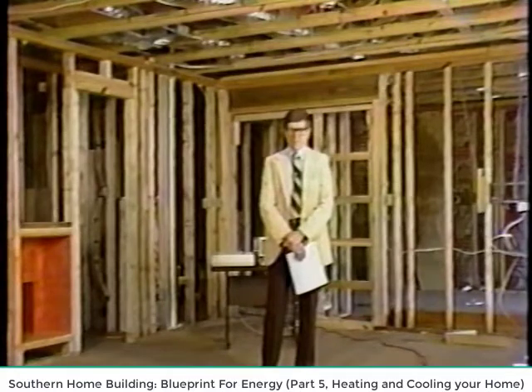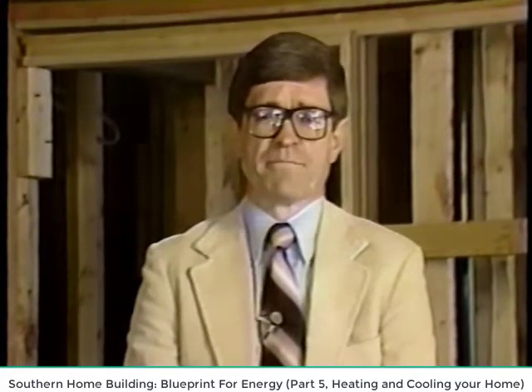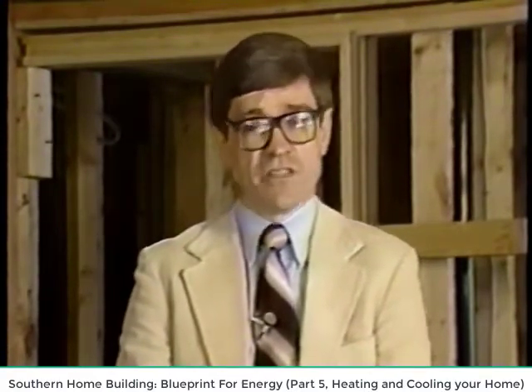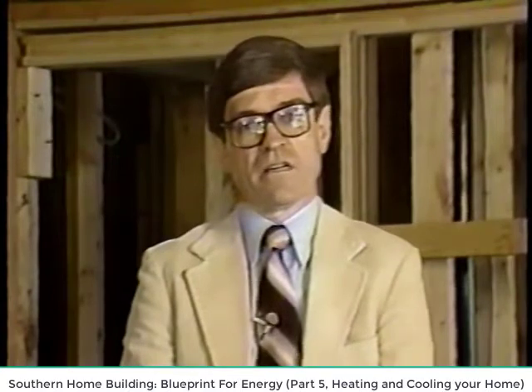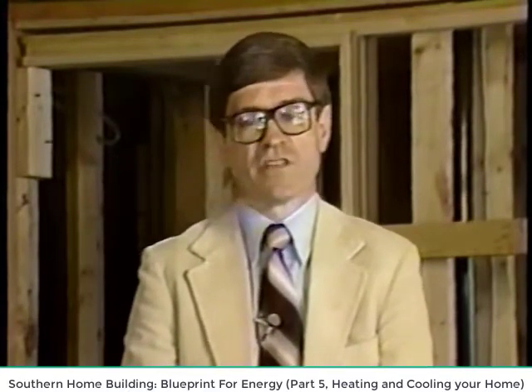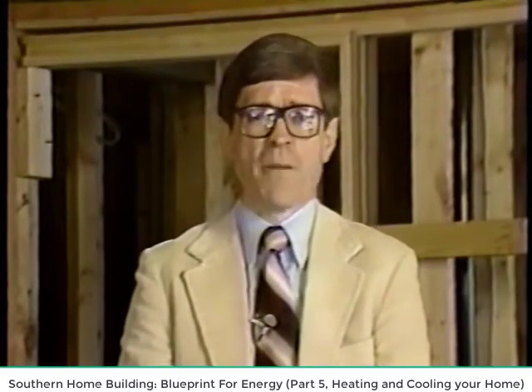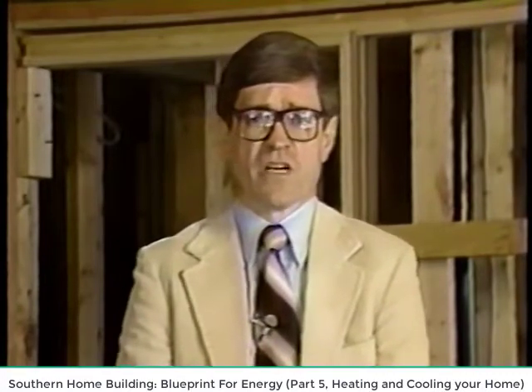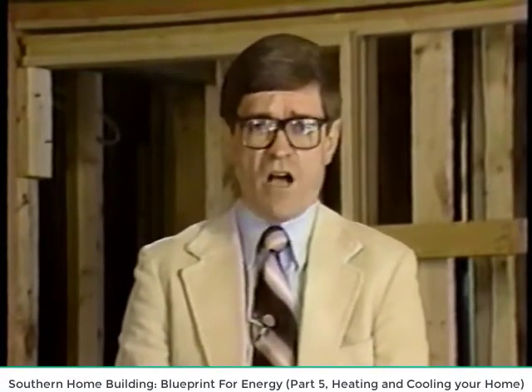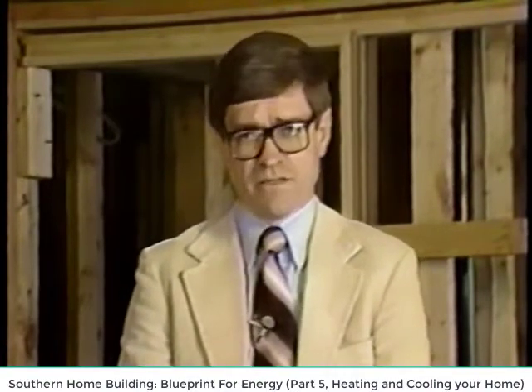and years of comfort. If the equipment is oversized, run times will be shorter, resulting in higher operating costs, and during the summer, higher relative humidity conditions during the off-cycle. A properly sized system should result in better comfort conditions in the house, lower operating costs, and a longer-lived system.